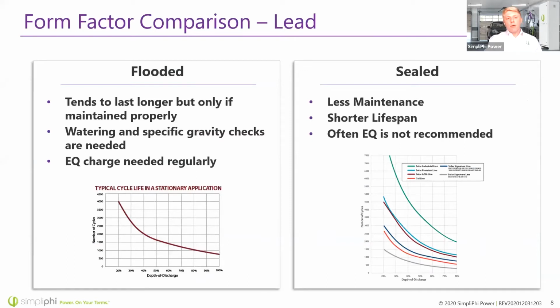I have found that flooded batteries last a bit longer, but only if you're really well maintaining them, requiring regular watering, specific gravity checks, and EQ charges. Sealed batteries don't last quite as long, but often EQ isn't recommended. You have the advantage of not maintaining the battery, so it's a trade-off: not lasting as long but not needing maintenance. On the right-hand side, note that gel and AGM are the two sealed battery types, shown as the dark red and bright red lines, and they don't last quite as long as the top flooded lead acid battery.